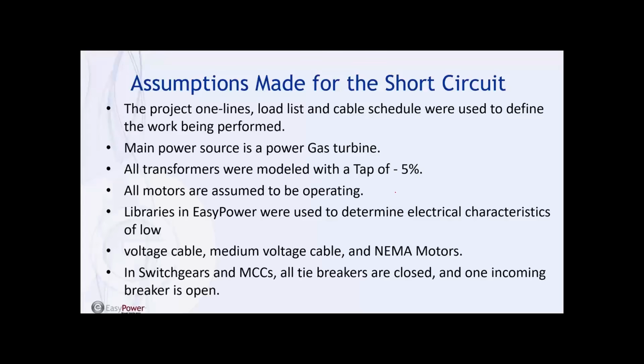Our main power source is the power gas turbine — remember this is an off-grid project, so we don't have the grid. An assumption made in this project: all power transformers were modeled with a tap of -5%. This means the impedance of each power transformer is lower, therefore the short circuit current is higher. We include all these assumptions only in the short circuit case, in order to have the worst scenario — the worst case to get the highest possible short circuit current. Another assumption made for this project: all motors are assumed to be operating. In real life that's not the case, but as I said, we're looking for the worst scenario.